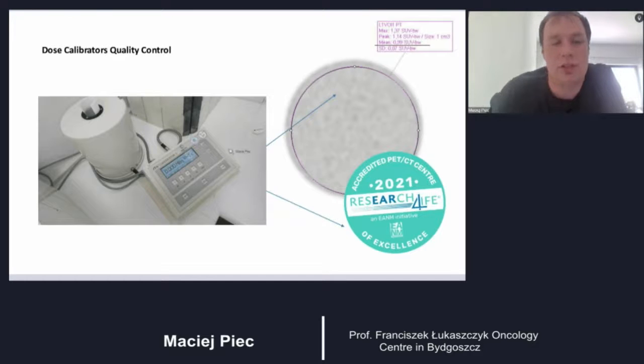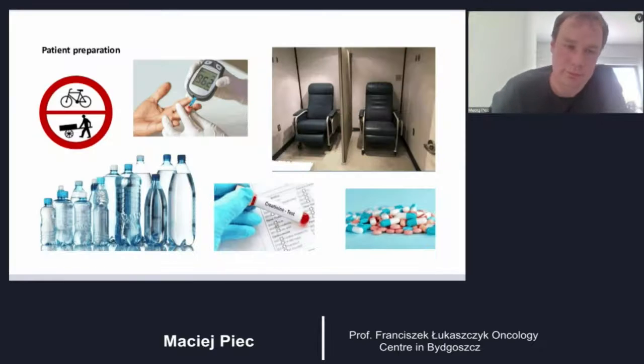So when we don't like the results, there may be 2 reasons. One is that there is something wrong with our PET equipment, and the other one is that there may be something wrong with the dose calibrator. So this kind of verification or validation before calibration seems useful. I myself, in my practice, once encountered a situation when this kind of validation allowed us to detect incorrect operation of the dose calibrator.